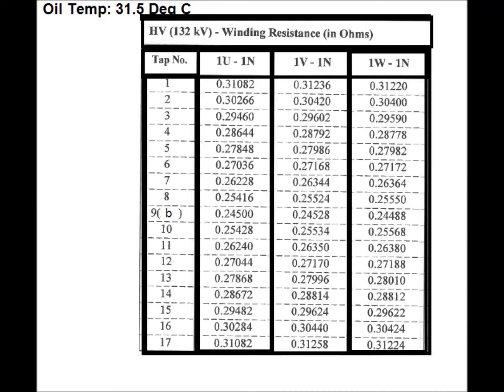In this table, the measured resistance for different tap windings is shown for the primary winding, R phase, Y phase and blue phase, for a YND1 transformer. Here the transformer capacity is 50 MVA. U represents the R phase, V represents the Y phase and W represents the B phase. The resistance measured at different taps is shown. It can be seen from the table that the measured resistance at tap numbers 8 and 10, 7 and 11, and 6 and 12 respectively should be almost the same.